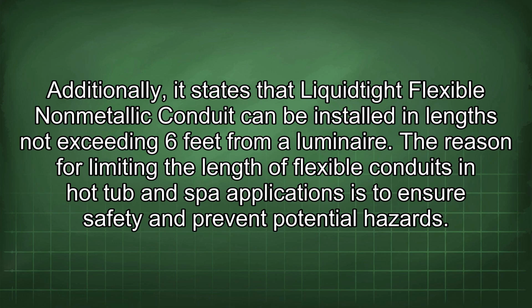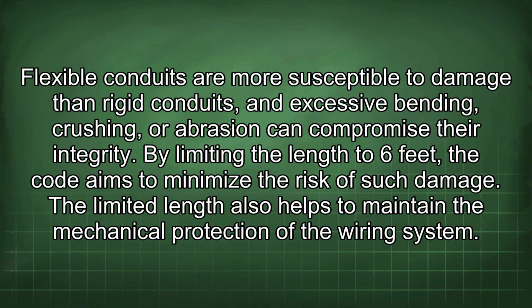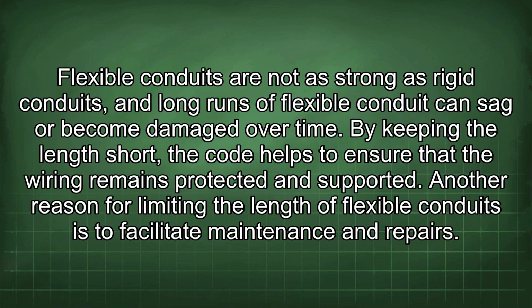feet from a luminaire. The reason for limiting the length of flexible conduits in hot tub and spa applications is to ensure safety and prevent potential hazards. Flexible conduits are more susceptible to damage than rigid conduits, and excessive bending, crushing, or abrasion can compromise their integrity. By limiting the length to 6 feet, the code aims to minimize the risk of such damage. The limited length also helps to maintain the mechanical protection of the wiring system. Flexible conduits are not as strong as rigid conduits, and long runs of flexible conduit can sag or become damaged over time. By keeping the length short, the code helps to ensure that the wiring remains protected and supported.